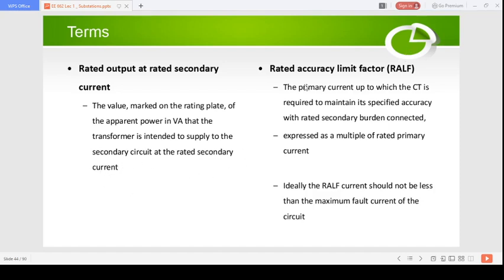Okay, and you have then the rated accuracy limit factor. The primary current up to which the CT is required to maintain its specified accuracy with rated secondary burden connected is defined as the rated accuracy limit factor. This is expressed as a multiple of rated primary current, so it is an integer multiple of rated primary current. Ideally, the rated accuracy limit factor current should not be less than the maximum fault current of the circuit.